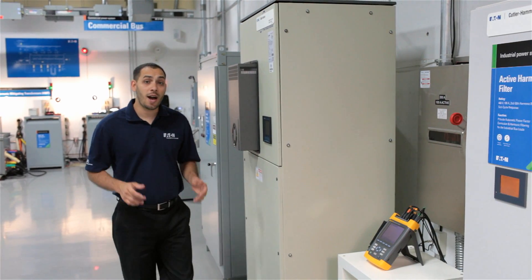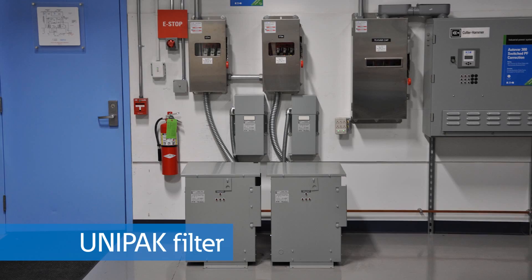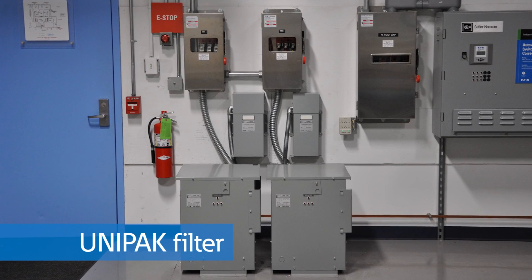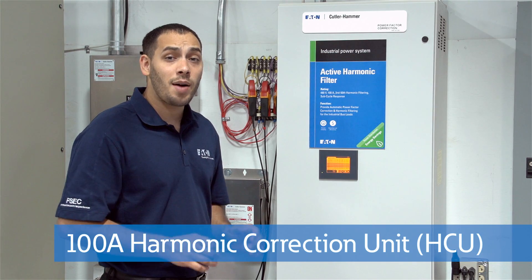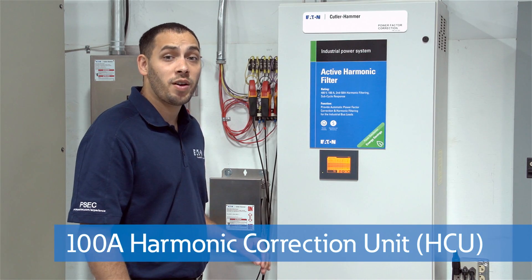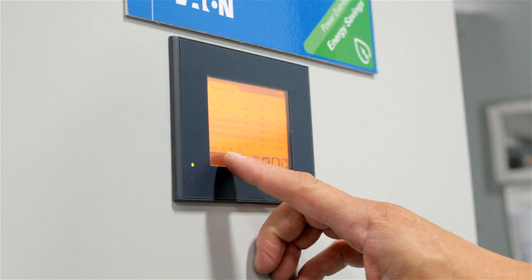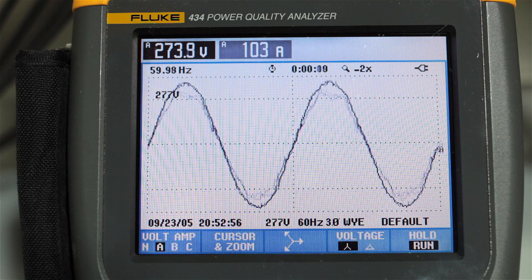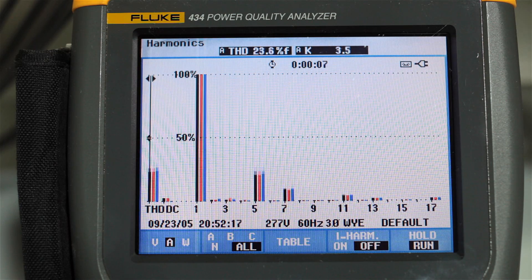There are several options available to you to reduce the harmonics in your system. A passive filter, such as this one, can be used to reduce the current of one or two harmonics. In systems with complex harmonic signatures or varying processes, active harmonic filters are a very effective solution. However, they are one of the most costly solutions. Active harmonic filters continuously monitor the non-linear load and filter as necessary.